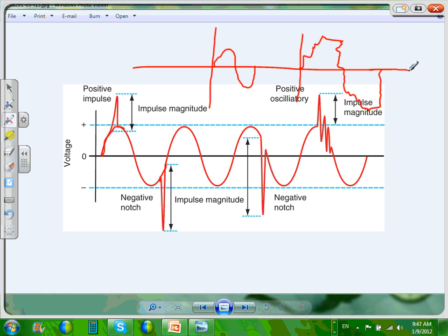The one underneath it, guys, is a pulse. This is why I think I drew some of these. We protect from a pulse here. If we have a pulse, meaning you switch a transmission line from one side to another, it will send a very high voltage for a very short amount of time. Who cares about very high voltage for a short amount of time? It burns equipment. So they have the TVSSs or surge protective devices that look at this short amount of time, connect you to the ground, and protect your equipment from it.